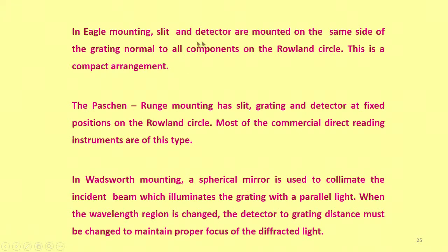So, in Eagle mounting the slit and detector are mounted on the same side, so that it saves the optical space, making the instrument compact.